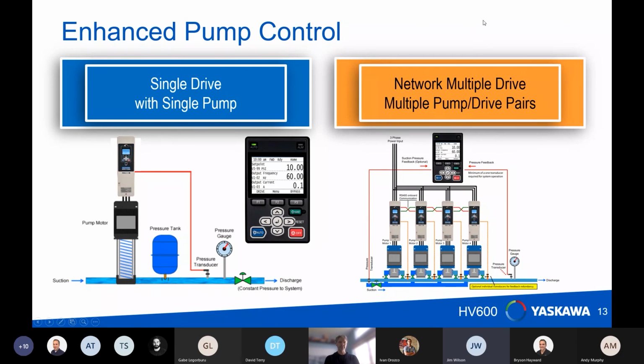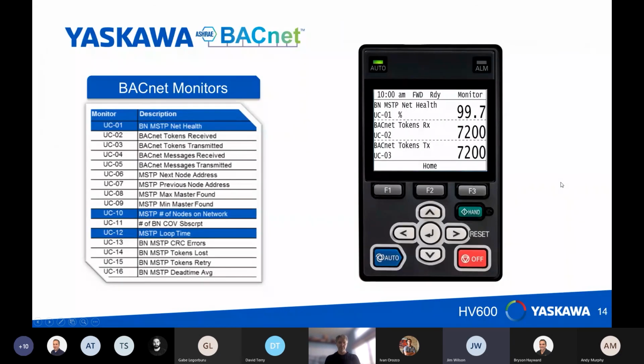We've added enhanced pump control for constant pressure, liquid level, or constant flow. This is actually a product, the software comes from a product that we've been doing for a long time in the irrigation industry. You can multiplex right out of the box, where you can still be connected to BACnet in your building automation system, but you run a single 2-wire conductor between the drives. You can set this network, multiplexing up network, menu driven in 15 minutes or less. It's very quick and easy to set up.